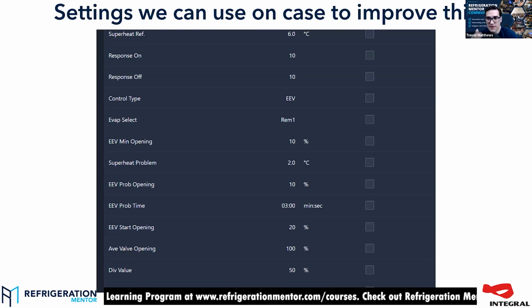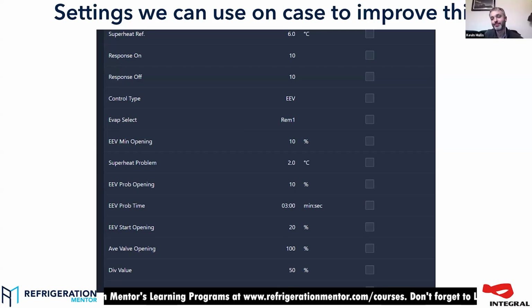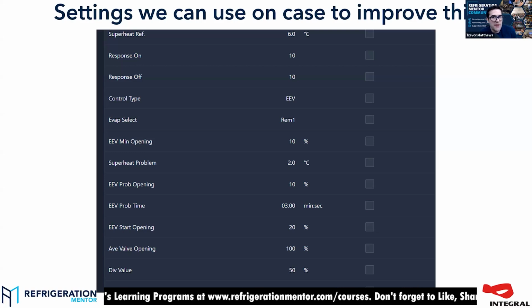And so there's no exact answer, because a lot of the technicians in the program, well, what is that answer to the minimum gas cooler pressure? It depends. Follow what the manufacturer says, because they're designing the system. And is it a split design? Is it not? Is it 700 psi? Because your 50 bar is 733 psi, and then you said 40, which is around 585 psi. But you want to follow the manufacturer, but there may be fine tuning for you.